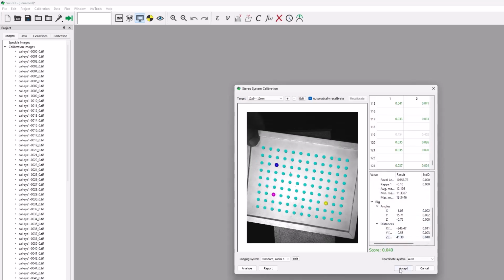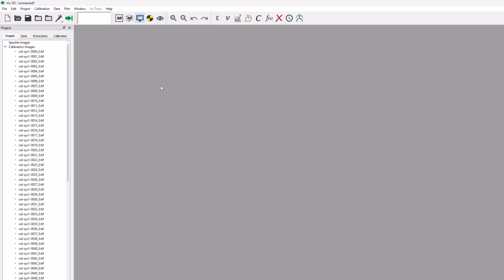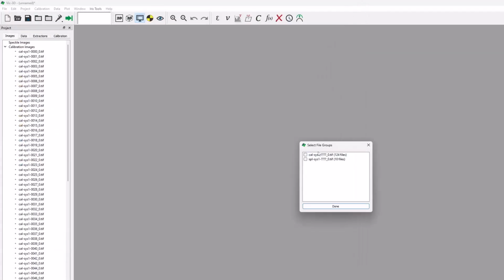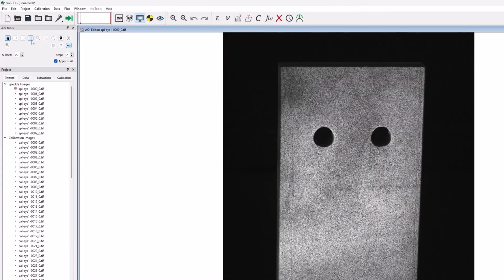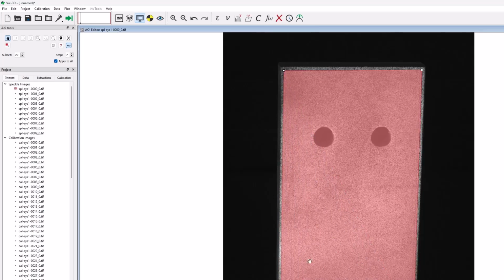After hitting accept, the system is calibrated and we can save and leave here. However, we'll do one final act, which is to add the hybrid cal. Go to Project, Speckled Image Groups, and import the SPL images out of the correct folder again. Use Draw Polygon under the AOI tools and draw the shape of the specimen in order to define the area of interest. You can use this opportunity to remove areas of no interest as well, such as the holes.